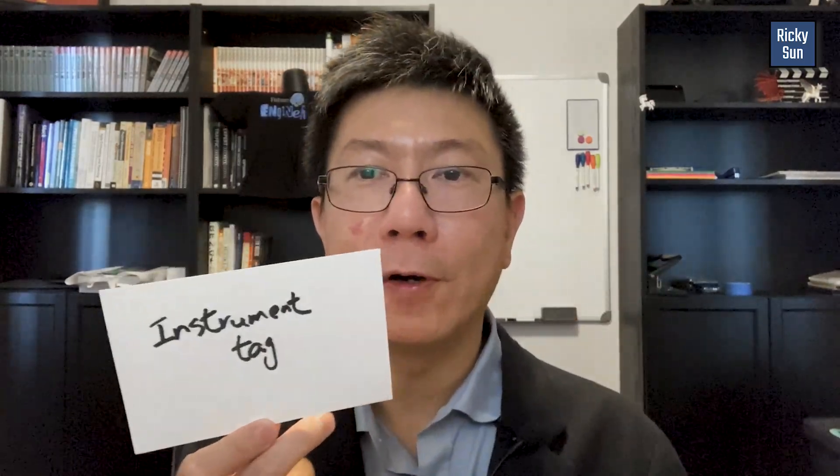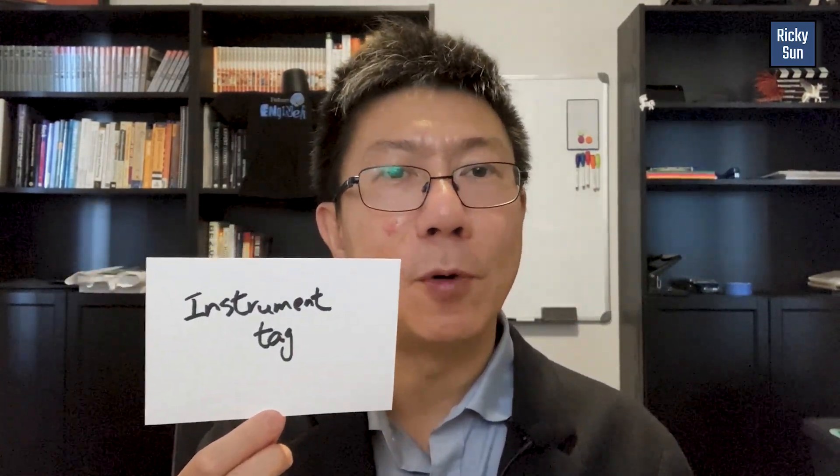I'm talking about the other attribute called instrument tag. This one is especially important for the OPC interface. Whatever item ID is in the OPC server, you have to have the corresponding item ID in the instrument tag attribute. You cannot have extra spaces or anything slightly off — it has to be the exact same item ID. Compression exception is the most common issue. I've worked with systems where the compression exception deviation is set to 100, but the data only moves by 0.1 or 0.2. That large deviation filters everything out, which is why you don't get data.